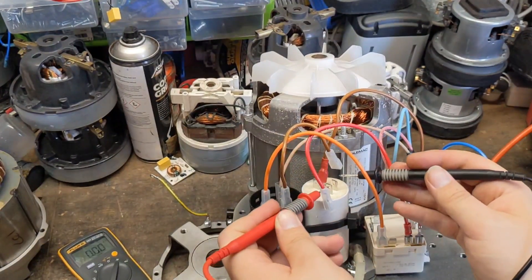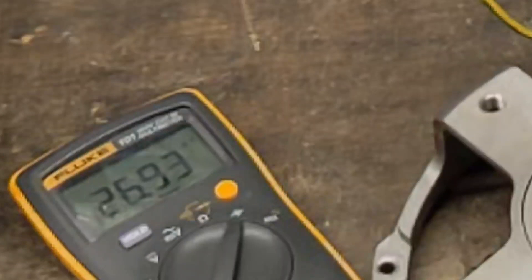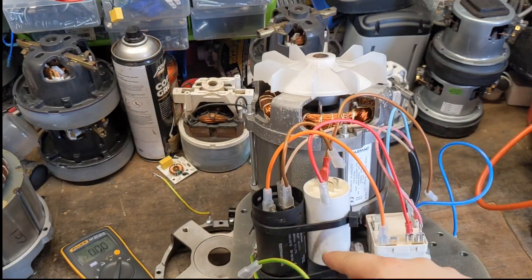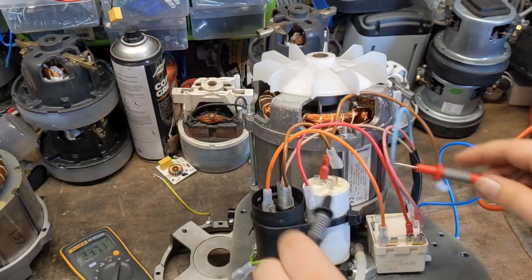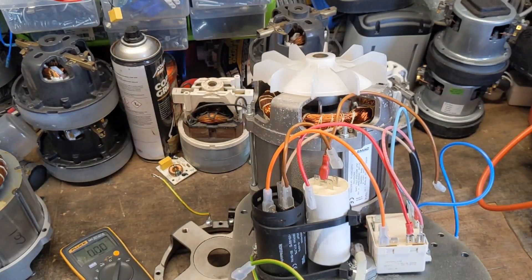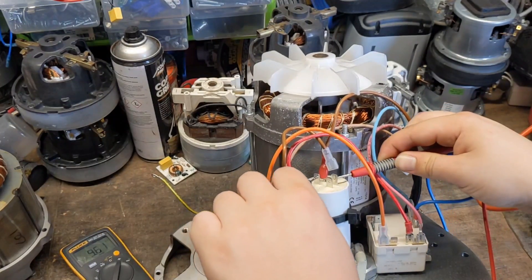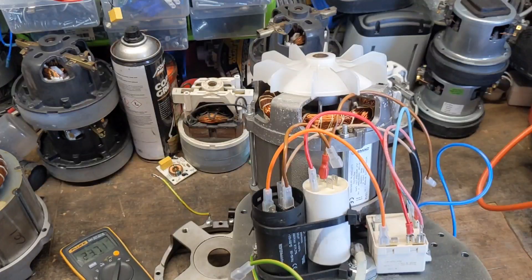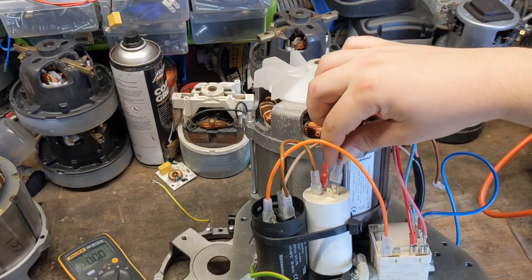So we've got the wires disconnected and we'll test the other capacitor again. We're getting 23.7UF. On this one it's rated 25UF plus or minus 5%, so 5% of 25 is 1.25, meaning the tolerance limit is about 23.75. We're just under — bang on the limit there. We'll leave that one in there simply because I haven't got another one of these 25UF capacitors at the moment.